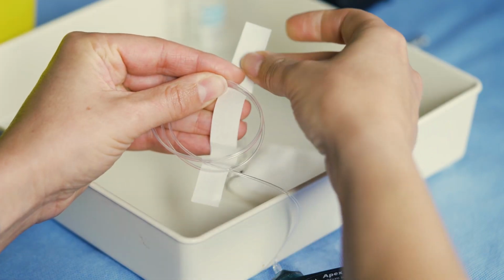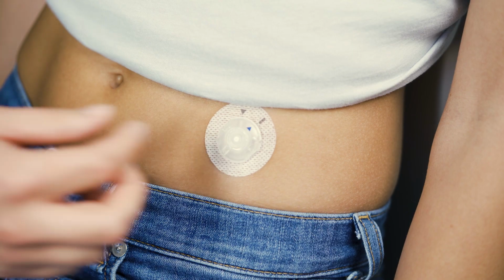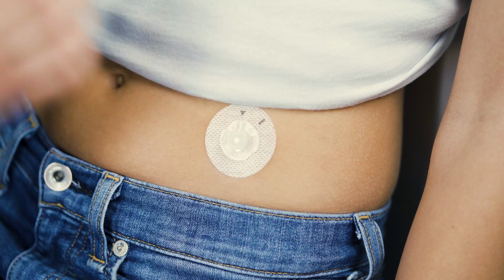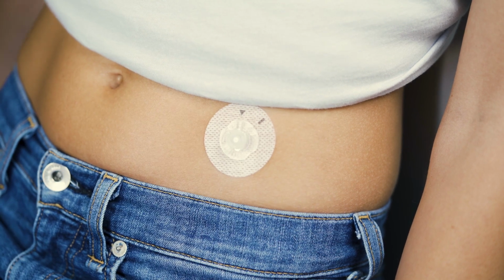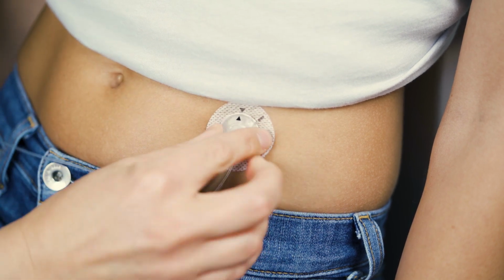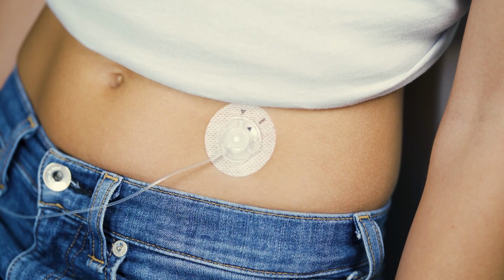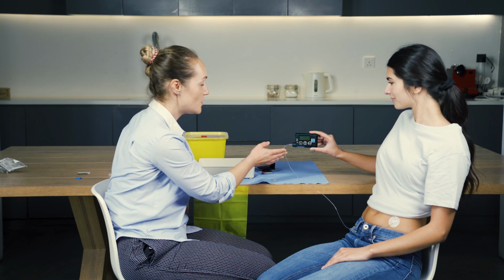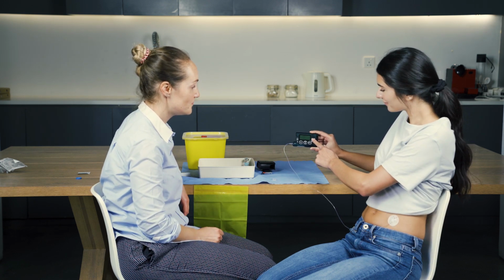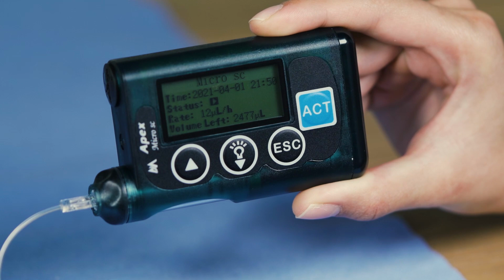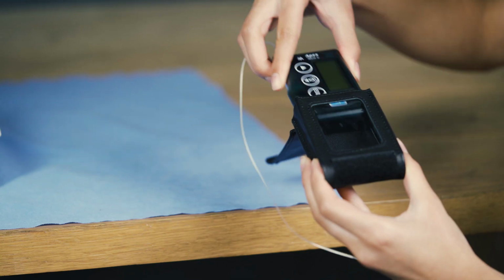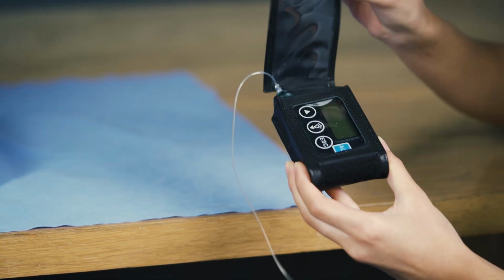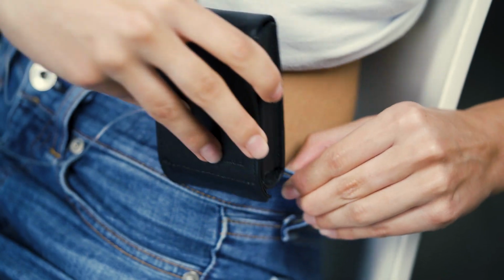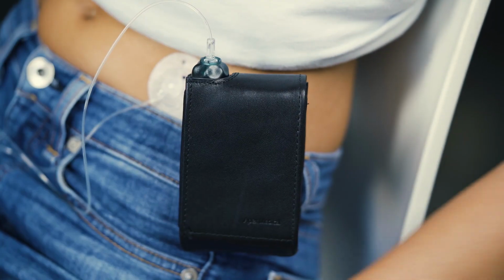First undo the paper tab, then remove the protection cap, and finally, connect the tubing to the cannula firmly. All you need to do is align the arrow with the line to secure it. Now that your pump is running and you've double-checked that the rate is the correct one and made sure that there's enough medicine to last overnight, place it in its case, attach it to your clothing, and you're good to go.